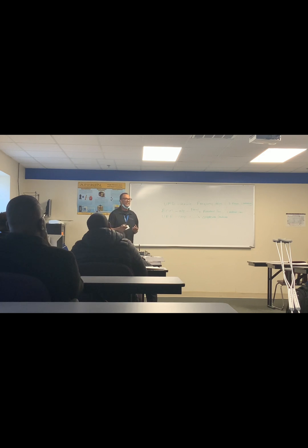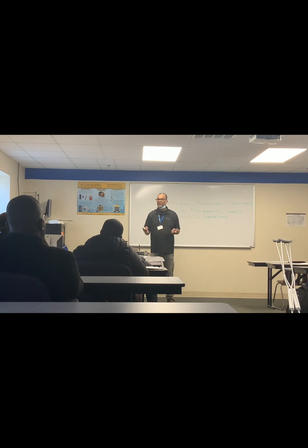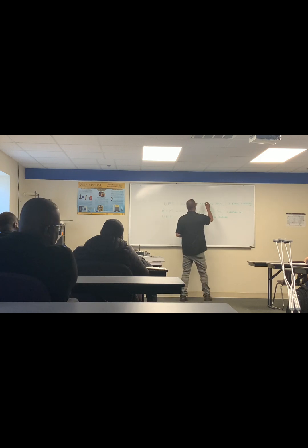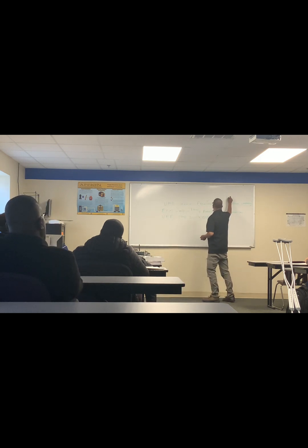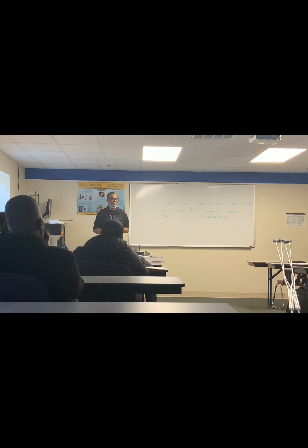And so you don't need any digital change to make the motor change speeds, because it's already 3-phase. Commercial's been using it for years to control pumps, to control fans, air handler fans. It'll speed up and slow down based on frequency, which is what? What is another word for frequency, do you know? Hertz. So 60 hertz would equal what percentage of the movement of the fan, or the motor, or the pump? 100%. So anything under 60 would be a slowing down of the motor, and it would be controlled by the hertz through the circuit, through the frequency drive.